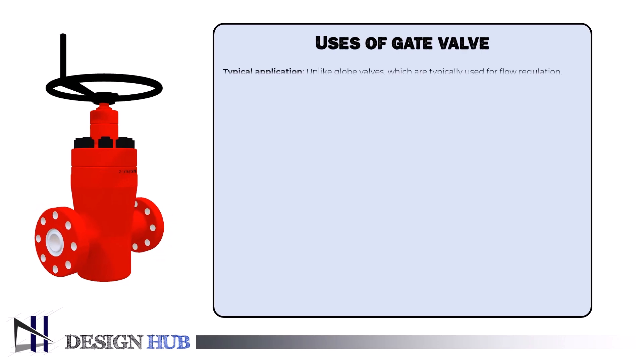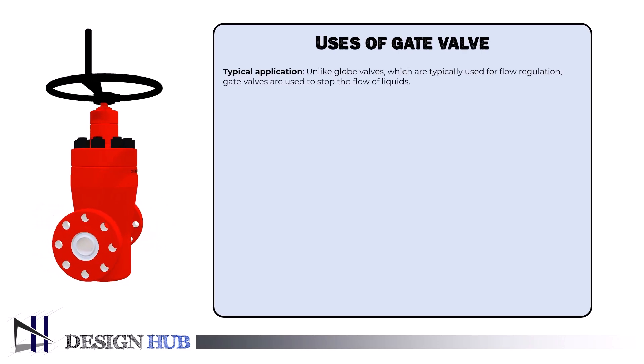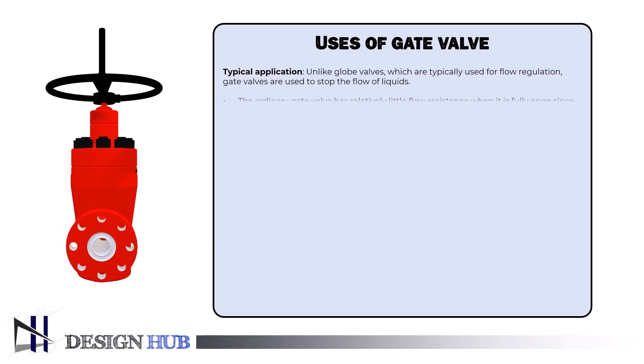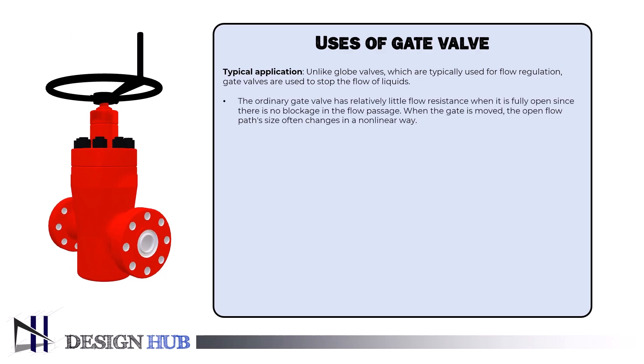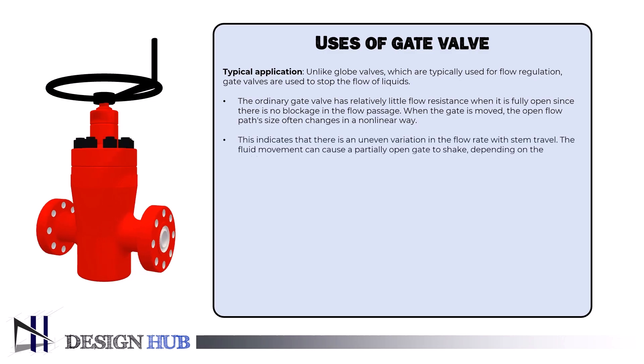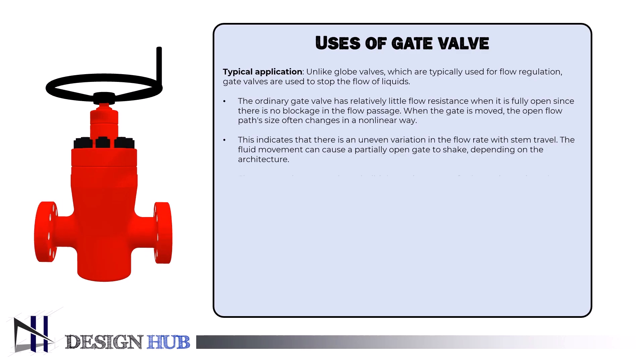Let's now examine the functions of a gate valve. Unlike globe valves, which are typically used for flow regulation, gate valves are used to stop the flow of liquids. The ordinary gate valve has relatively little flow resistance when fully open since there is no blockage in the flow passage. When the gate is moved, the open flow path's size often changes in a non-linear way, indicating an uneven variation in the flow rate with stem travel.